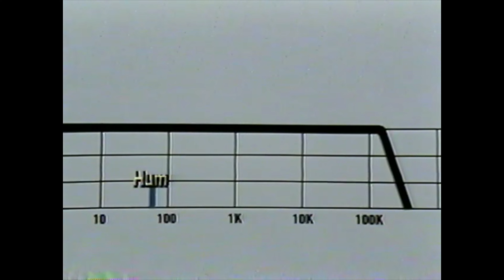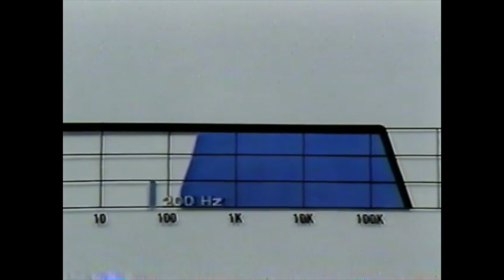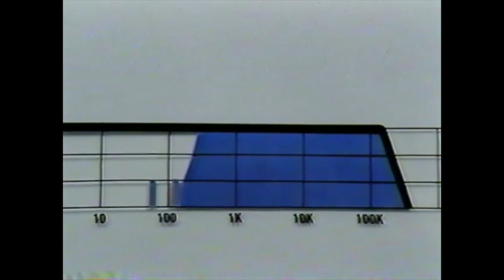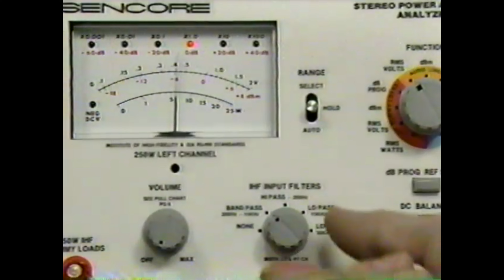Hum from power supplies or ground loops may mix with your test signal. Hum filters use a cutoff frequency of 200 hertz to include both 60 hertz power line interference and the 120 hertz frequency from a full wave power supply. You find the amount of hum by comparing the meter readings without filters to the readings with the hum filter switched into the meter circuit. The difference is the amount of signal added by the hum. You use the other filters in a similar way to find high-frequency noise.